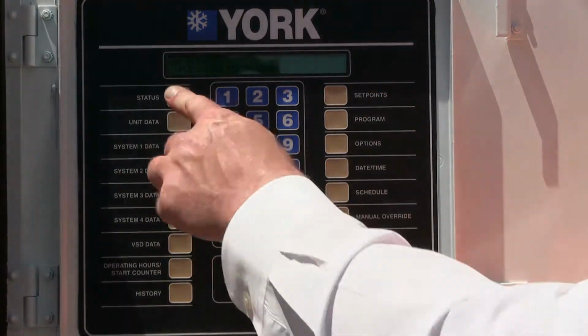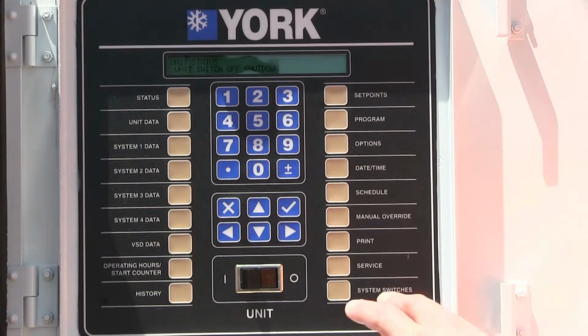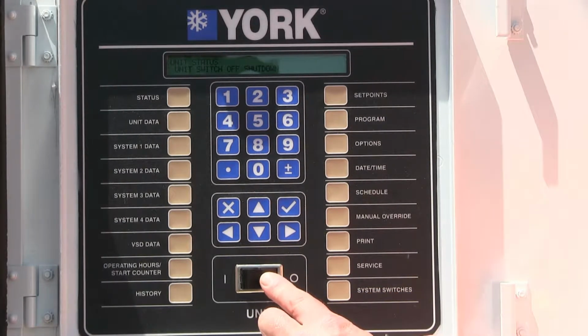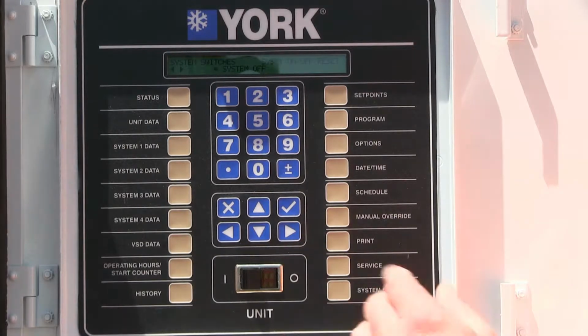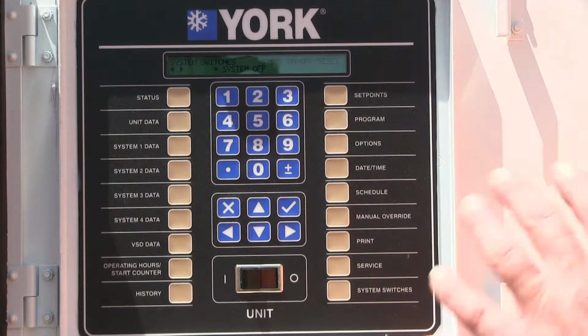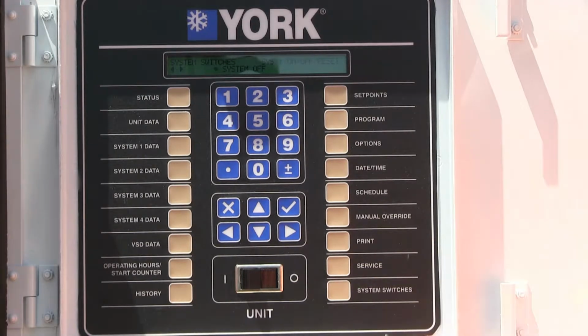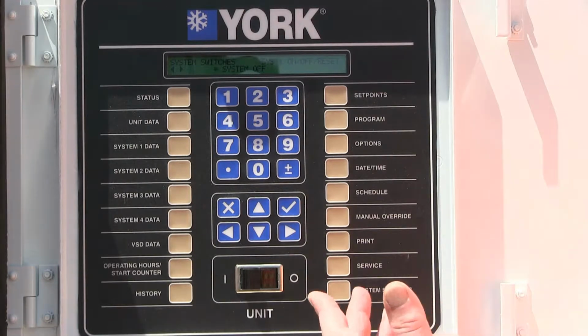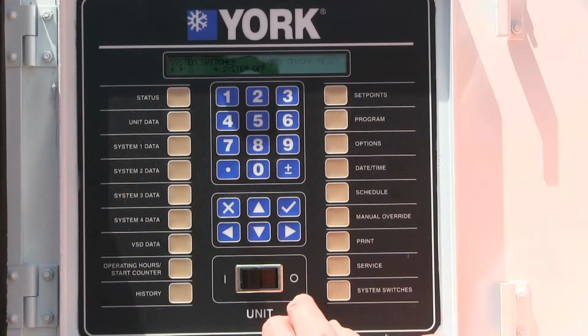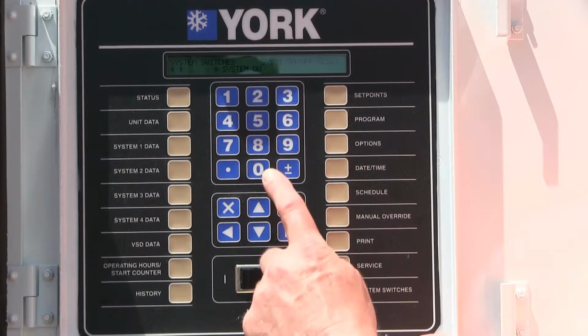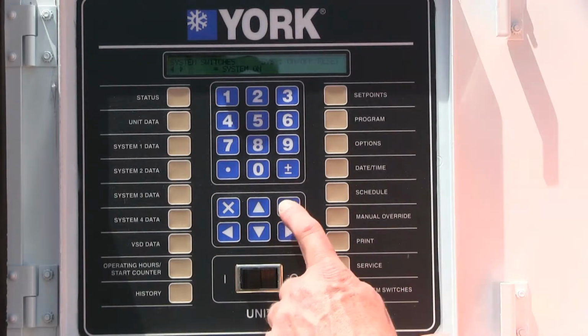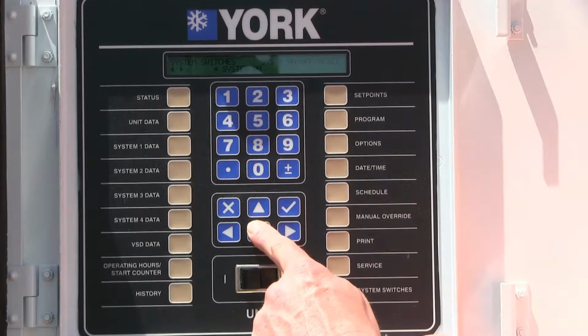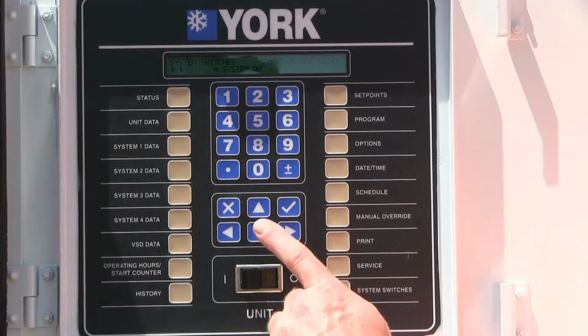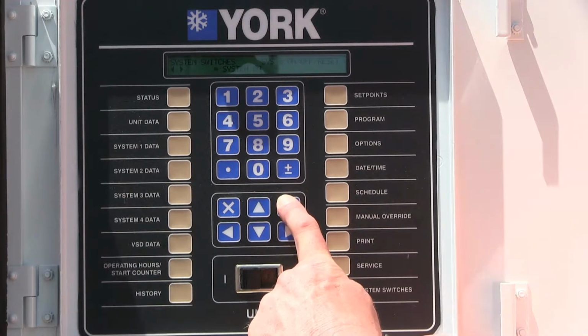And then we go back to status, and then probably one of the most valuable buttons here is going to be your system switches. And notice it said unit switches off here, but under system switches, this is where we actually turn system 1 on or system 2 on, or vice versa. 1 off and 2 on, or we can turn both of them on. So right now you can see I've got system 1 is off, and I want to turn that system on. So I'm going to move my arrow over to on. I'm going to say enter there. Then I'm going to go down to system 2, and I'm going to move my arrow over and make it say on. Now I'm going to push the check mark, enter there.